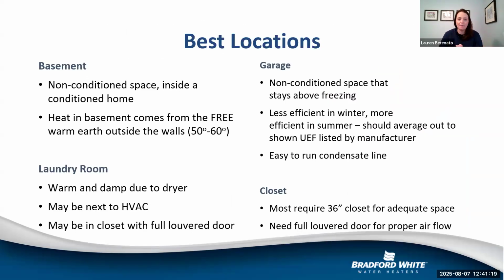Best locations for heat pump water heaters: garages are really popular. The reason for this is the open air, as well as heat pumps will often cool the temperature of a room anywhere from 3 degrees to 5 degrees. It all depends on your climate. If it's warm, it's really great to have it be cooler. If it's cool, it's not great to have it be cooler. So it really comes down to that. Basement, closet, laundry room. Just make sure that if you are in a closet, the same way you would for an atmospheric venting, that you have a full louver door for proper airflow going through.